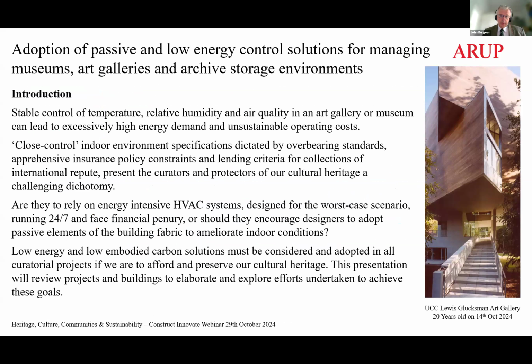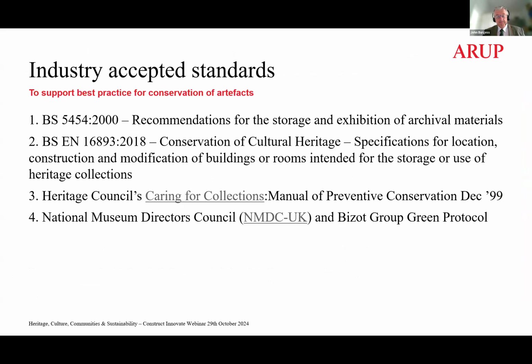A key issue for galleries, museums, libraries, and archival storage is how to do it in the most energy efficient way. We're plagued with overzealous standards requiring 21 degrees plus or minus half a degree at 50% plus or minus relative humidity, which leads to crazy amounts of energy consumption. We do get a small leniency on RH, plus or minus 5%, but that in itself is not enough.